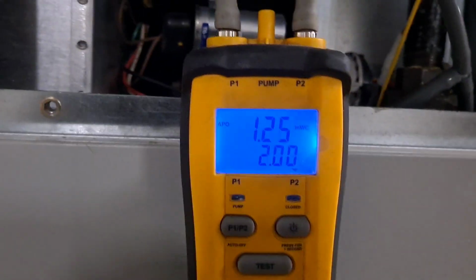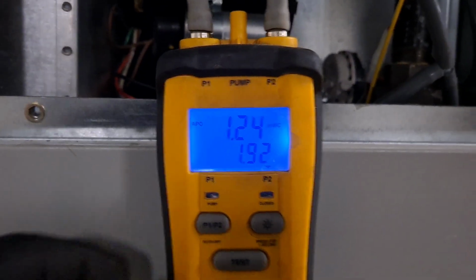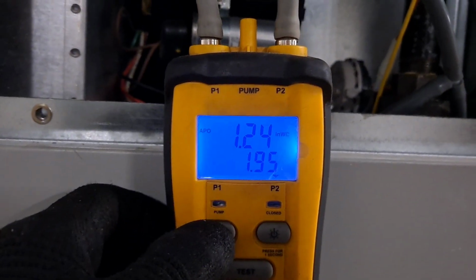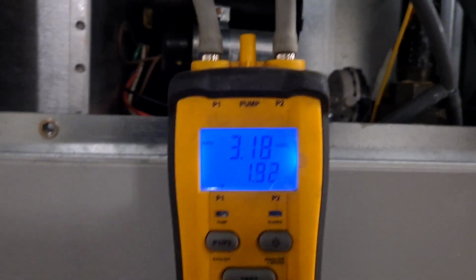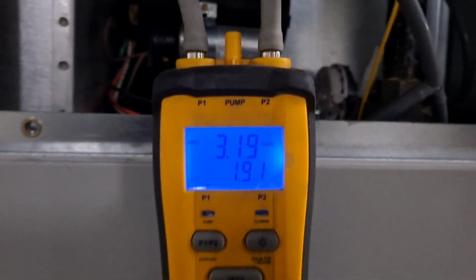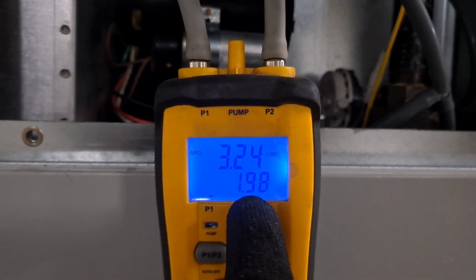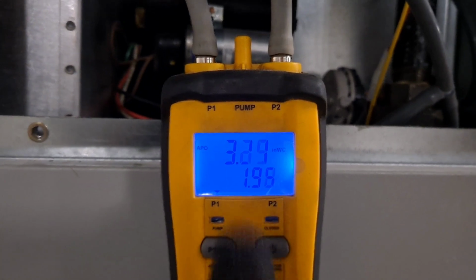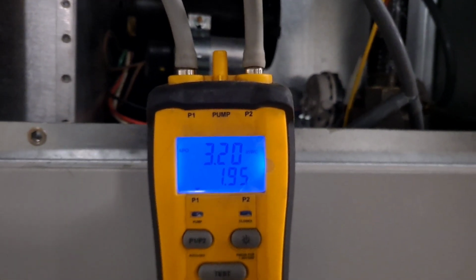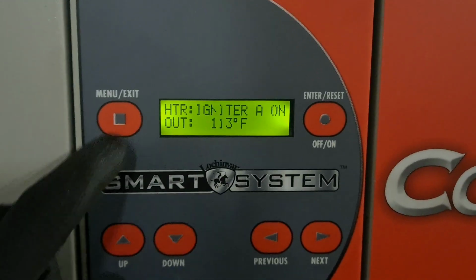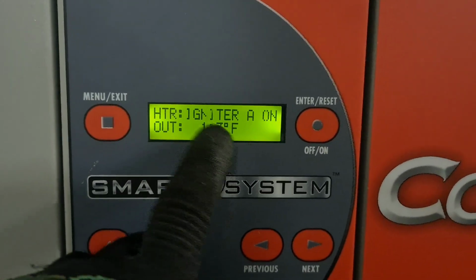little too high. So my chamber pressure, 1.25, which is perfect because it should be between 1.2 and 1.3. But my differential, which is my manifold pressure, is a little high. So that needs to be adjusted down to 1.8. Okay, so now all I gotta do is reset the service reminder on this.